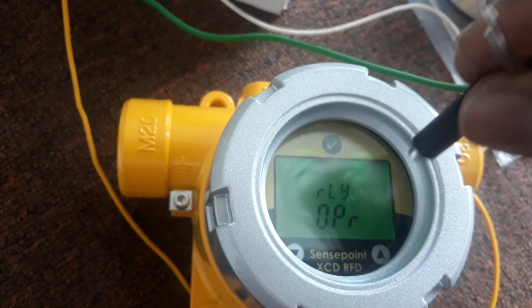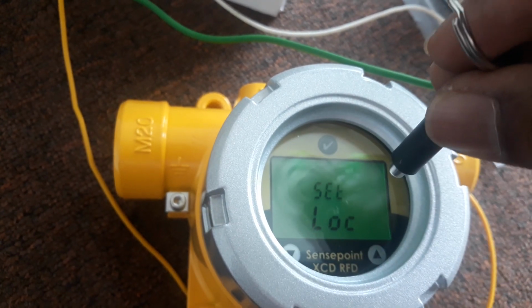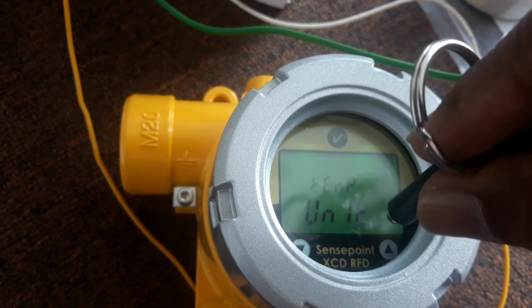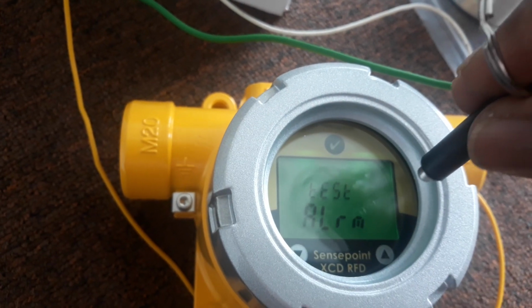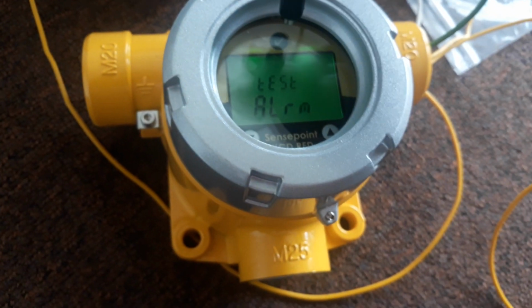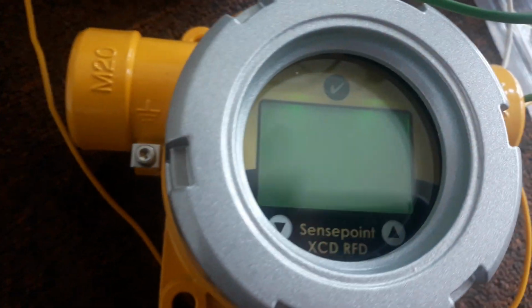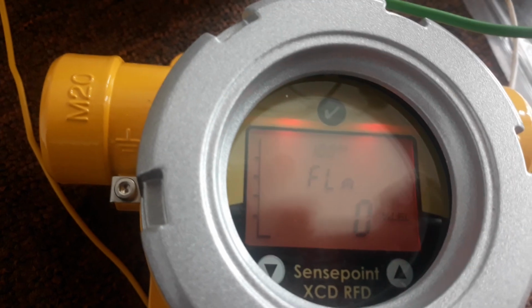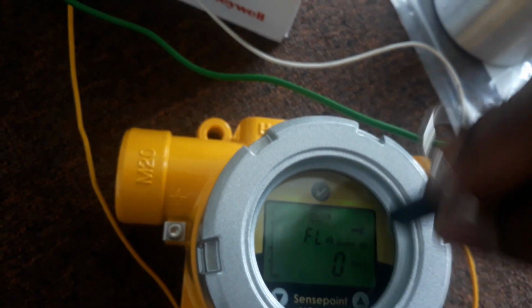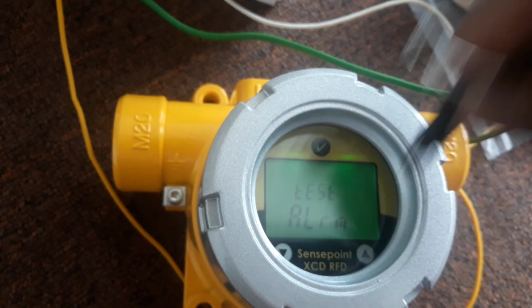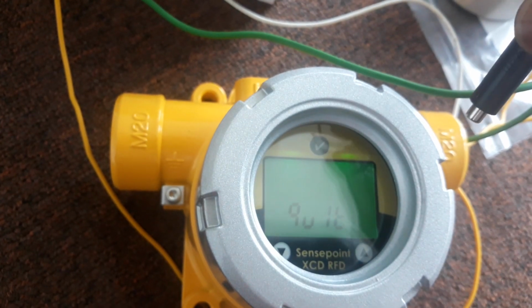So you can set the relay. Set lock if you want lock. This one you need for temperature. Test alarm, if you want to try the test alarm, you can push here. Okay, first alarm. I force the first alarm, you can see the relay trigger and then the blinking. When you see the red color blinking, it means the controller shows an alarm, something wrong with your sensor. Okay, test alarm done. If you want to set the ID, you can set the ID and then quit.